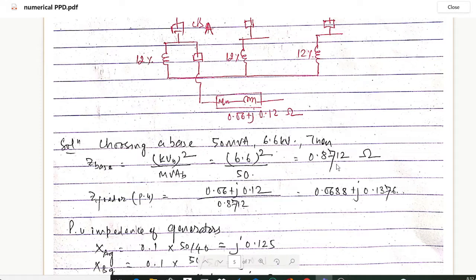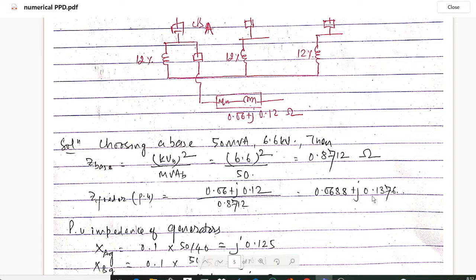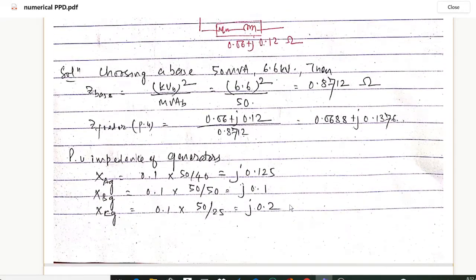The impedance of the feeder in per unit is calculated by dividing the feeder impedance by the base impedance. With feeder impedance of 0.06 + j0.12 ohm divided by 0.8712, we get Z_feeder = 0.0688 + j0.1376 per unit.